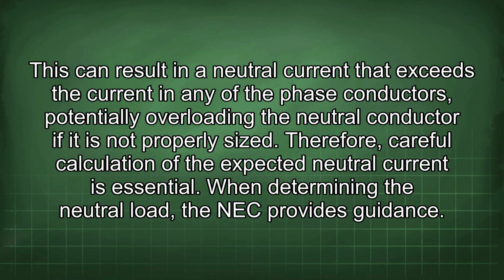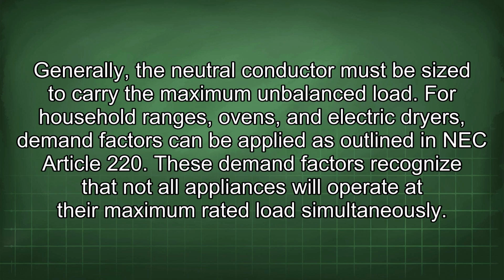This can result in a neutral current that exceeds the current in any of the phase conductors, potentially overloading the neutral conductor if it is not properly sized. Therefore, careful calculation of the expected neutral current is essential. When determining the neutral load, the NEC provides guidance. Generally, the neutral conductor must be sized to carry the maximum unbalanced load.